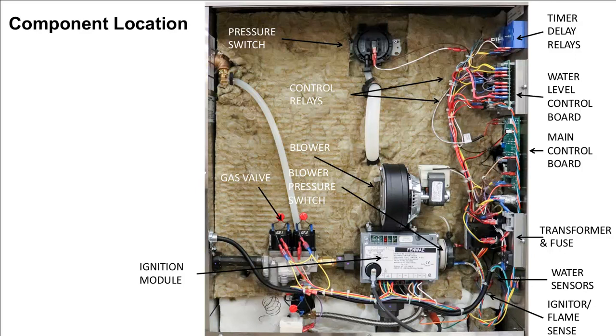And before we continue, I'd like to draw your attention to the gas valve. When you are troubleshooting a gas steamer, I highly advise you to connect your manometer as the first thing you do. There is a port on the right-hand side of the gas valve. You connect your manometer in there using an 1/8" NPT. This will help you greatly in testing the call for heat, and I'll go into details on that as we go through the presentation.